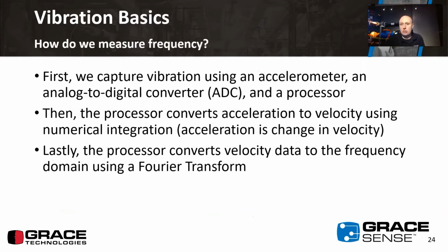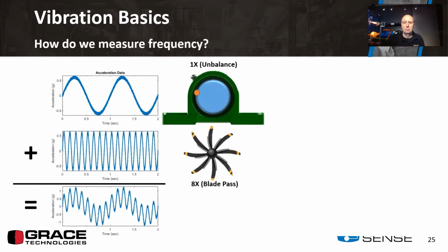So how do we measure this frequency? Well, first, same as before, we put an accelerometer on the asset, capture that data, and convert it from analog to digital form into a processor. That digital form allows the processor to deal with it. It then converts it from acceleration to velocity for the reasons we just talked about, and then takes that velocity data and moves it into the frequency domain using what they call a Fourier transform. Here's an example of how this works out.